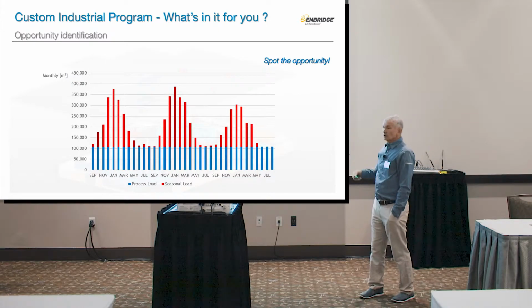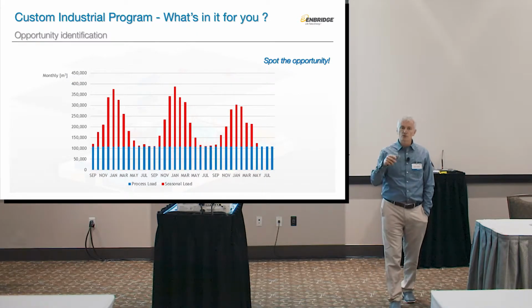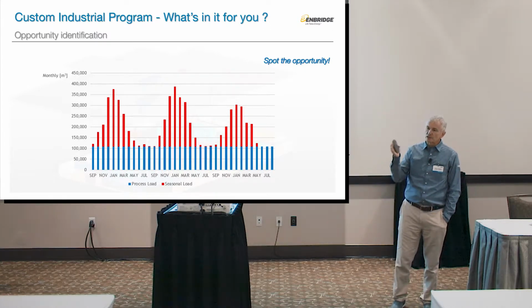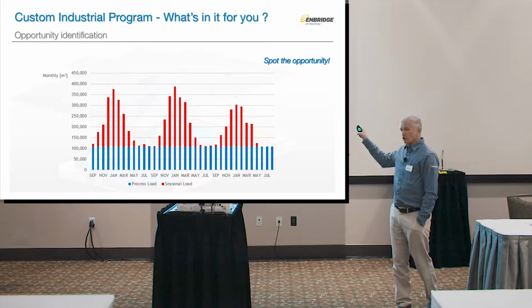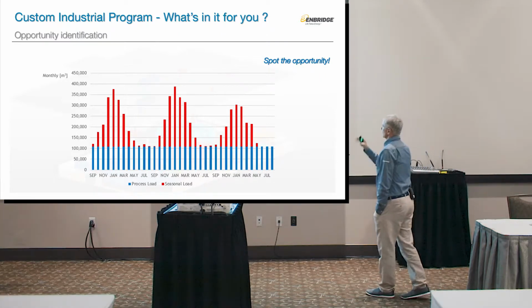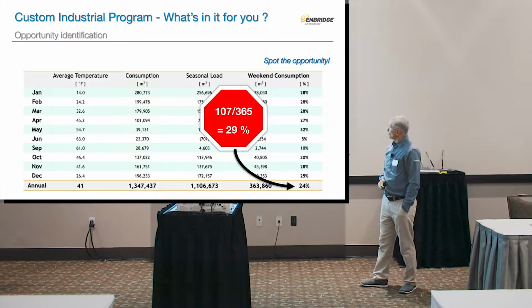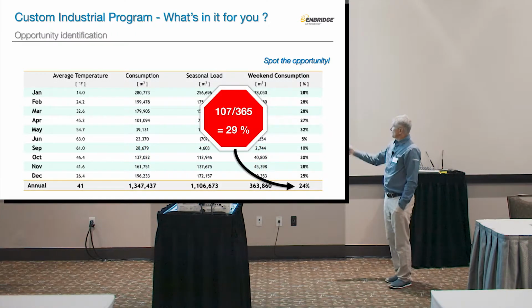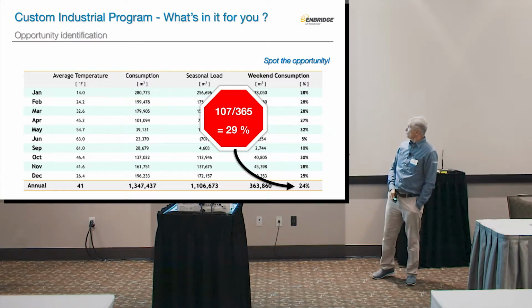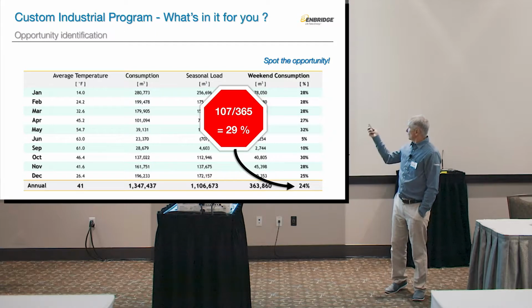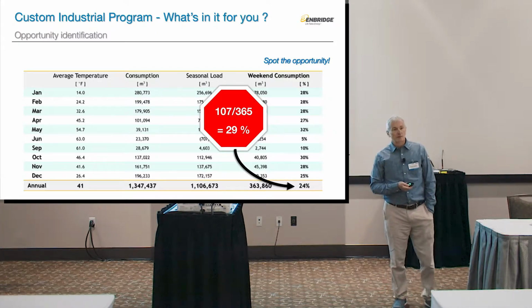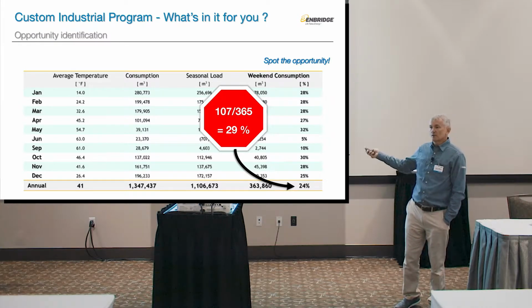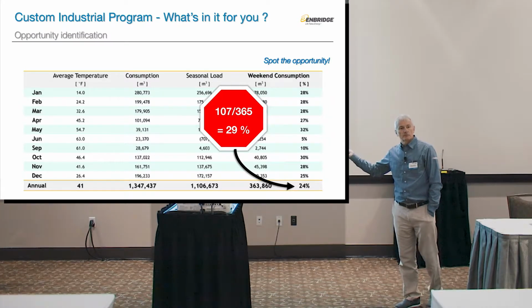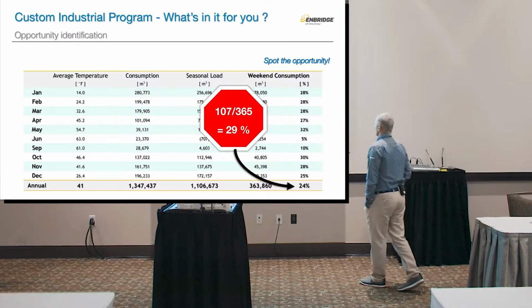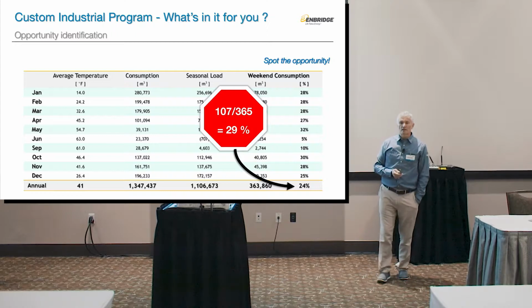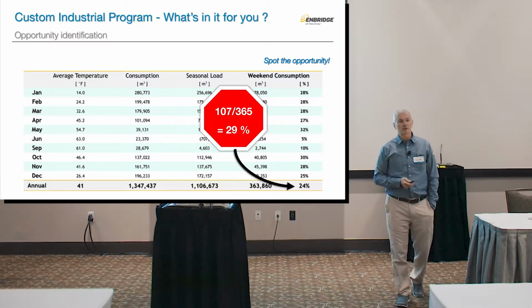Third one, if you look at your consumption over 3 years, and I use a 3-year average because that avoids the slight peaks if a year was especially difficult or if it was warm or whatever. If you look at the consumption and you put it in this way, and then you look at where the consumption actually went, in this particular example, 24% of the consumption was on the weekends, and weekends and non-working days represent 29% of the year. And then the customer tells you, oh, I'm working 24/5. So that's an obvious opportunity to ask, why is your consumption on the weekends the same as on any other workday if nobody is in the facility?